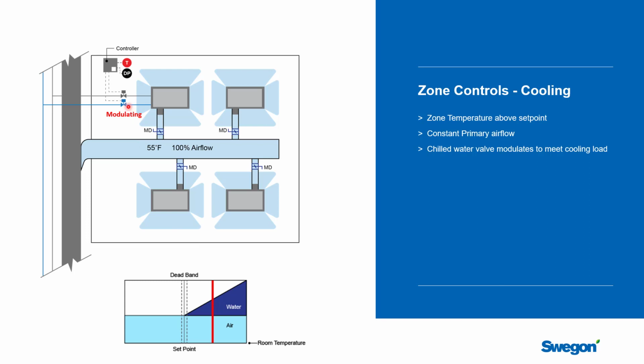Now you'll notice that there's only one valve. This is a good recommendation to help manage the capital costs of the project, is to have one chilled water valve and one hot water valve for the whole control zone. And so that when this valve opens, it will actually let water go to all 4 beams. And if you needed hot water, it would also allow that hot water to go to all 4 beams. You don't want a situation where one beam is opening its chilled water valve and then the beam over here is opening its hot water valve. So there's an advantage in having one valve per control zone.